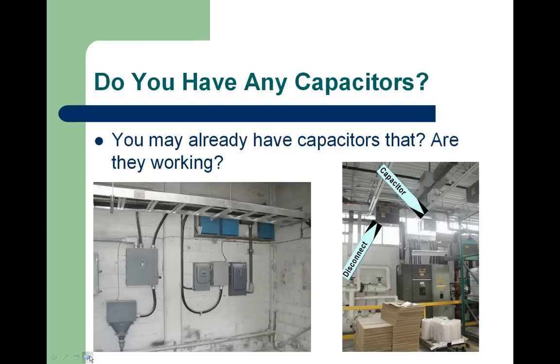One of the things that's happened over the years is we've been called out to sites, and people will say, we're interested in putting in power factor correction. We go, we have a look at the site, and in some cases they actually have capacitors. Sometimes the customer doesn't even know they exist or they've had them. And in some cases they're turned on, and in some cases they're turned off. So anybody in the maintenance end, they come in many, many different sizes and colors, as you can see here.